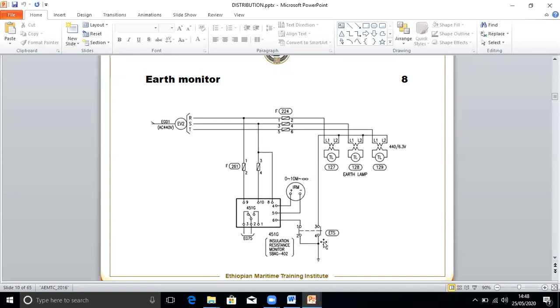At the same time, you can see three lamps also connected here. Whenever any one of them has dropped, you'll find it becoming dim. So these lamps should have equal brilliancy. Whenever there is an earth fault, you'll find the lamp becomes dim. Okay, this is the earth test switch. When you want to simulate it, you switch this on, and this is the ground. So you make it ground here, and you can test this alarm with this earth test switch.